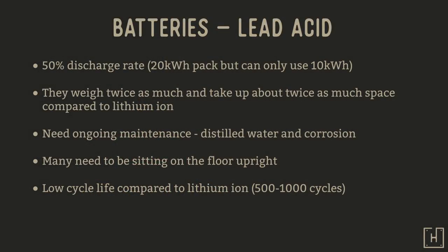They weigh about twice as much and take up about twice as much space compared to lithium ion. They also need ongoing maintenance. So if you ever hear people say they have to top up their batteries, they have to fill it up with distilled water. Also, around the connections on the batteries, they can corrode over time, and they should be cleaned up every once in a while.